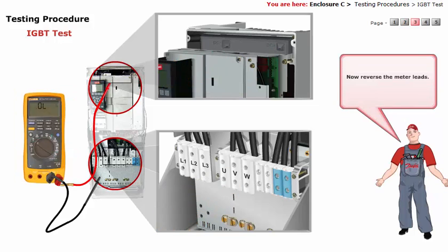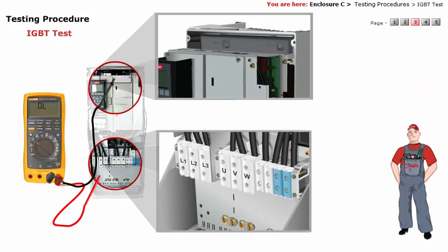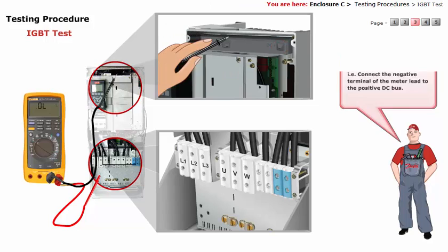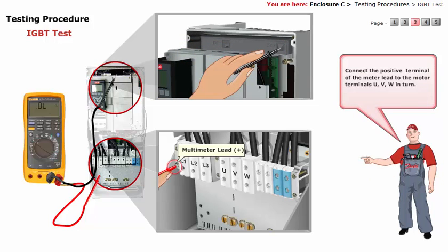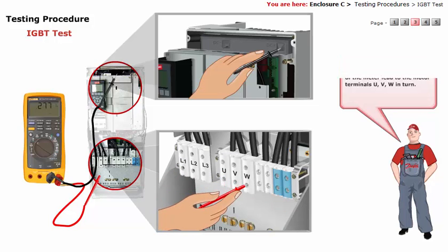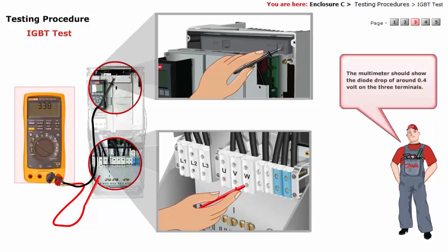Now, reverse the meter leads. That is, connect the negative terminal of the meter lead to the positive DC bus. Connect the positive terminal of the meter lead to the motor terminals U, V, W in turn. The multimeter should show a diode drop of around 0.4 volt on the three terminals.